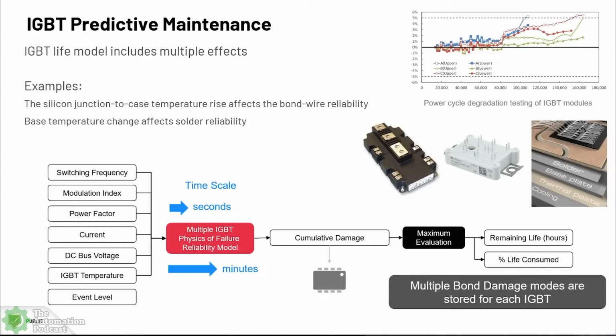A great example of that is something as simple as temperature changes inside the device that negatively impact the bond wires inside the drive, or inside the IGBT. These are bond wires here on the right-hand side. Over time, you get some thermal fatigue and those break - unfortunately that's a wear-out mechanism of this device. So how do we create a model around it?